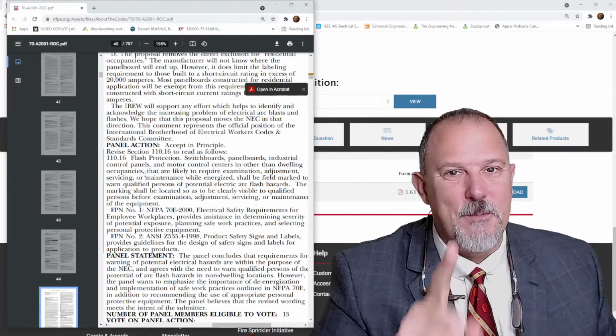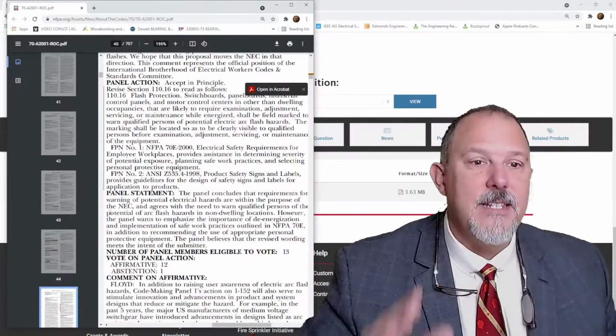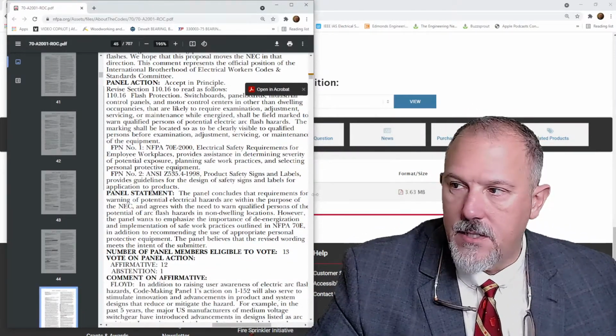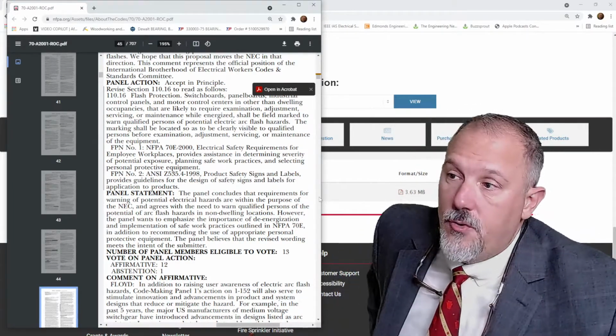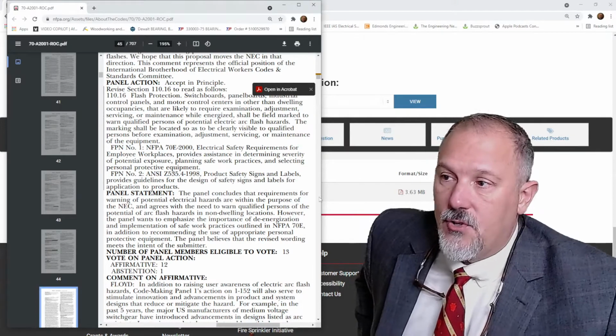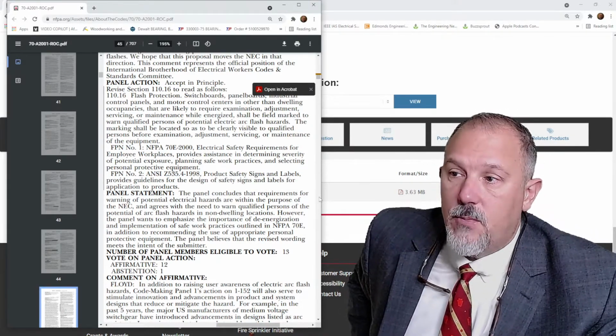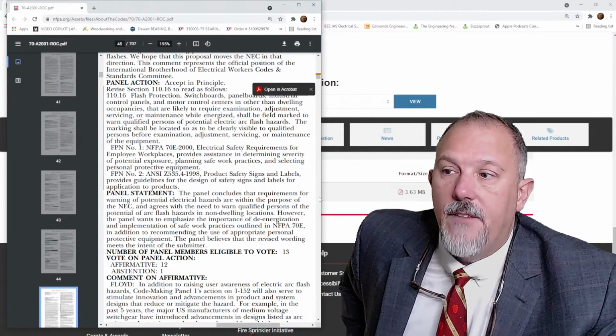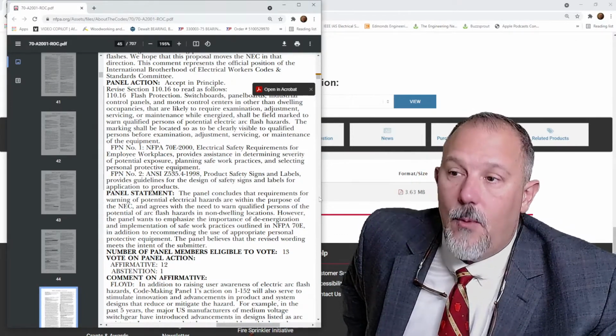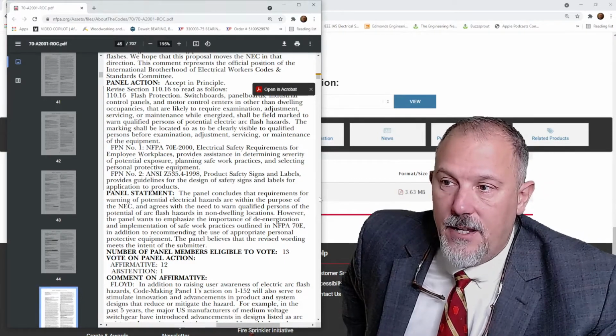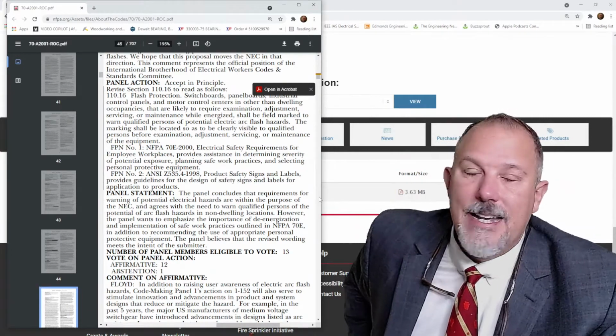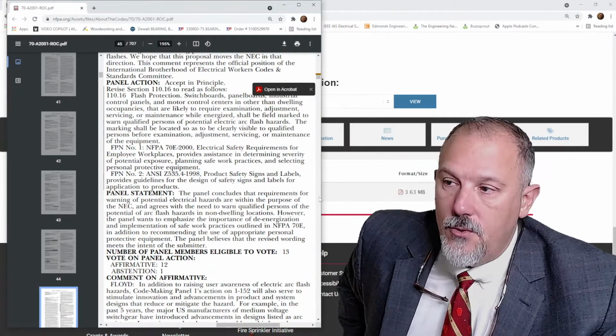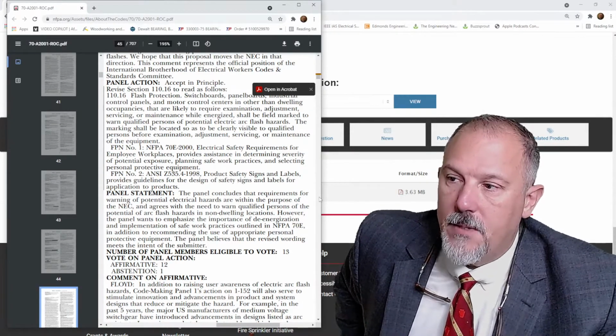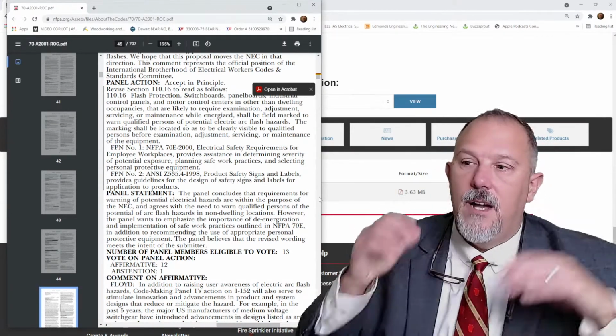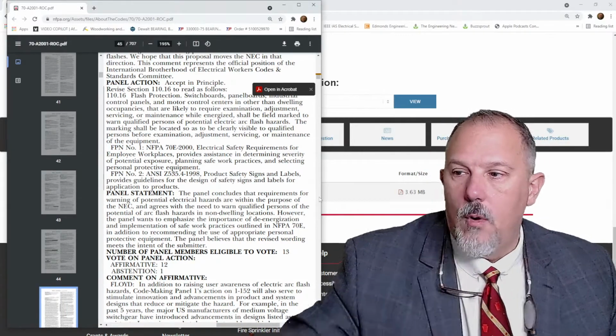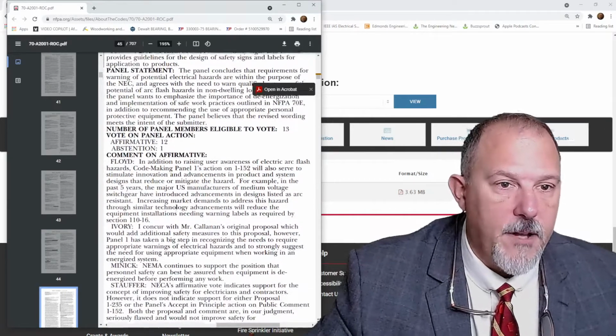Remember, they called them fine print notes back in the day. They weren't informational notes. And this is their panel statement, a statement that's typically voted on by the panel. The panel concludes that requirements for warning of potential electrical hazards are within the purpose of the NEC and agrees with the need to warn qualified persons of the potential of arc flash hazards in non-dwelling locations. However, the panel wants to emphasize the importance of de-energization and implementation of safe work practices outlined in 70E, in addition to recommending the use of appropriate personal protective equipment. The panel believes that the revised wording meets the intent of the submitter. 12 affirmative, 1 abstention, and there are some comments on affirmative.